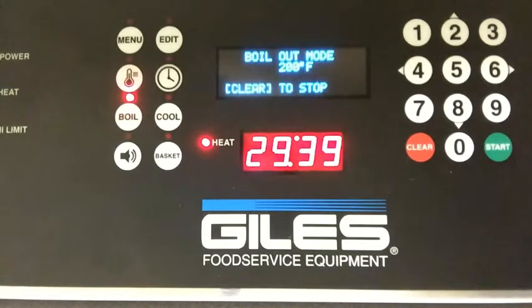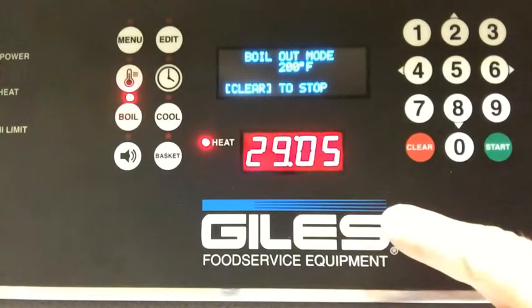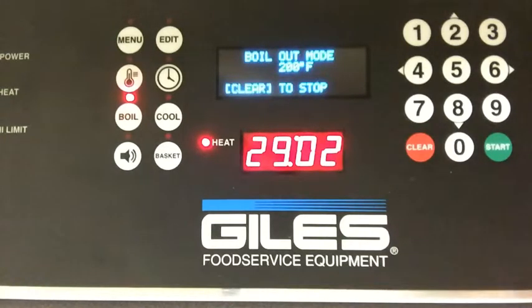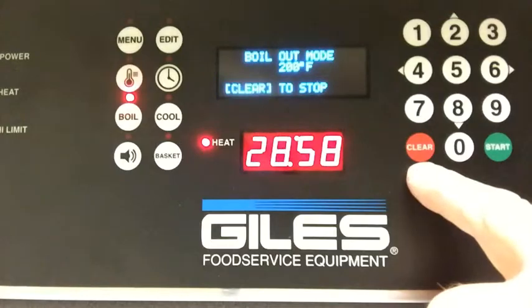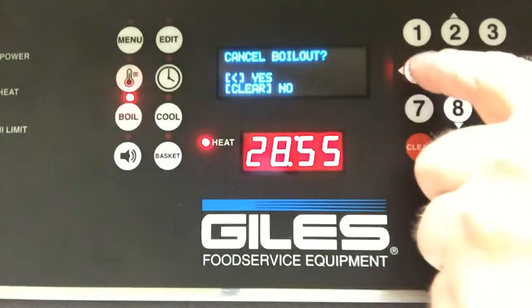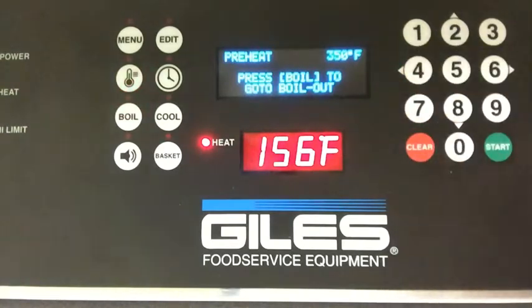In high altitude areas, you may want to make an adjustment, and we will be able to adjust this in a little while. You may want to adjust this to 190 degrees because you actually do not want it to boil out. You want the water to just be really hot, but not actually boiling. 212 degrees is an actual boil. And of course, if it heats up to 200, when it shuts off, it's going to start to boil, because it shuts off at 200, but with the residual heat in the elements, it's going to overrun that 212 degrees. So we're going to clear, and then we have to hit that left arrow to actually do it so that it's not accidental, and we're back out of there.